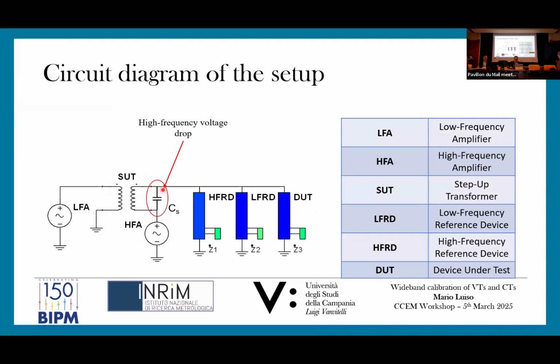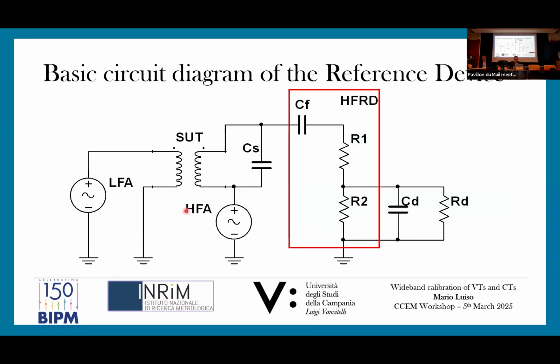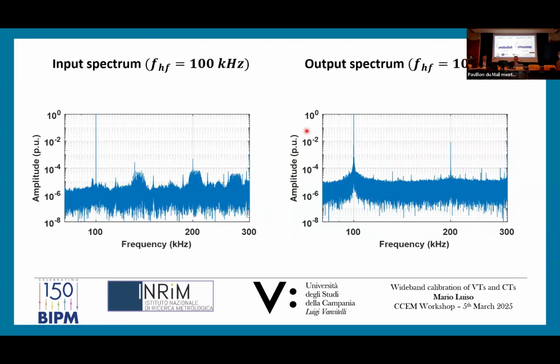It is something like Ilya showed this morning. And also the measurement of the generated voltage was split: the fundamental tone was measured with a commercial divider. Instead, the high frequency components were measured with a homemade divider that has a high pass behavior. So it is able to measure just the high frequency component from 9 kilohertz up to 150 kilohertz.